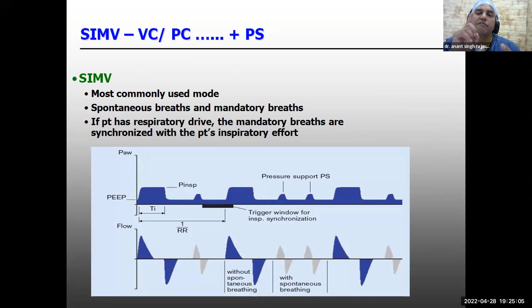Okay. So we developed something called SIMV mode. So synchronization. What happened in synchronization? We get a time window. Okay. So there is a window that we are getting. During that window, suppose I say that the patient is to be ventilated with a respiratory rate of 15. So every 4th second, one breath will be given. So we get a window now. From the 3rd second to the 5th second, we make a window. Okay. Now what happens during this phase? If the patient triggers during this phase, the mandatory breath is converted into an assisted breath, right? A mandatory breath is converted to an assisted breath and the ventilator skips the mandatory breath. So there is no hyperventilation. So this is synchronization with the patient. Okay. That is why it is called synchronized intermittent mandatory ventilation. This can be done along with volume control mode or it can be done with pressure control mode.